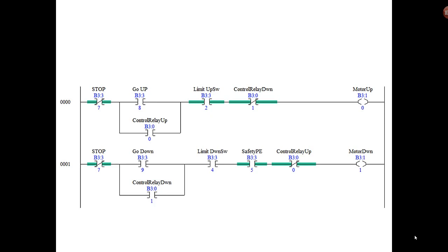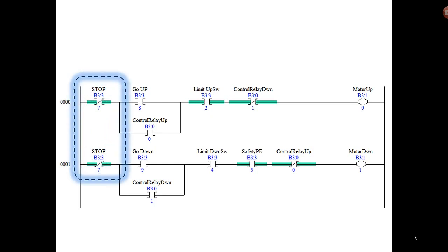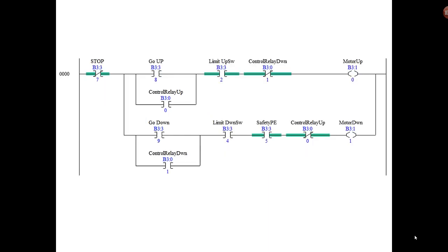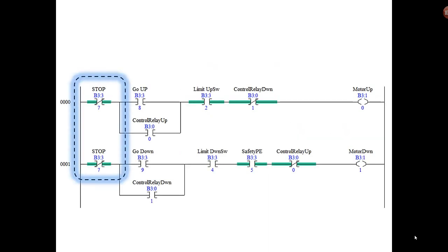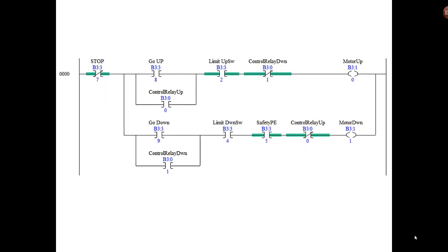Notice that we eliminated the control relay up and control relay down and combined them. Now there's a few more changes we have to make yet, so don't run off to the store to buy your parts. Also, we wanted to get rid of the two stop instructions. There's really just one bit that we use, B3:3/7, so we'll combine that into one because that condition or permissive is common to both rungs.